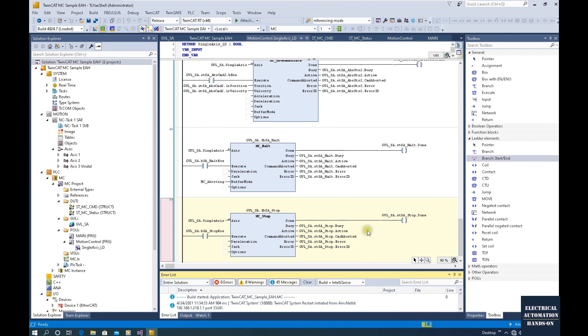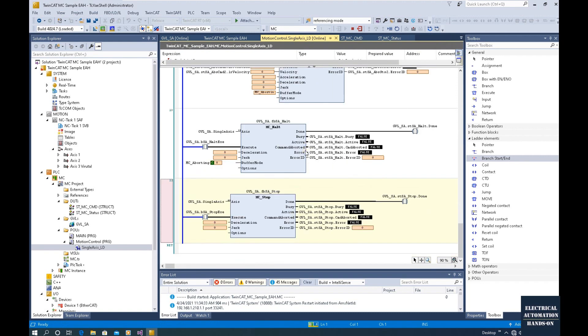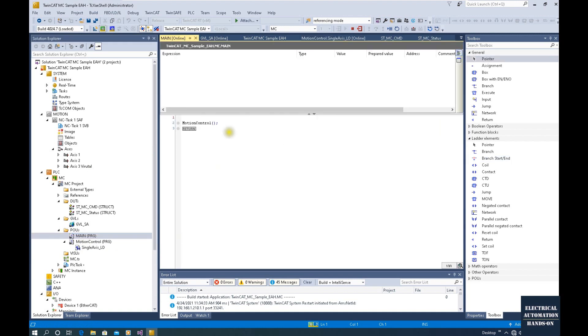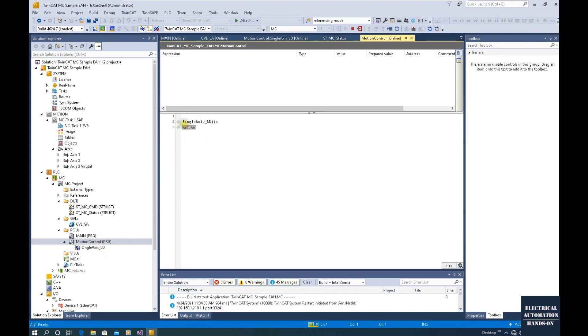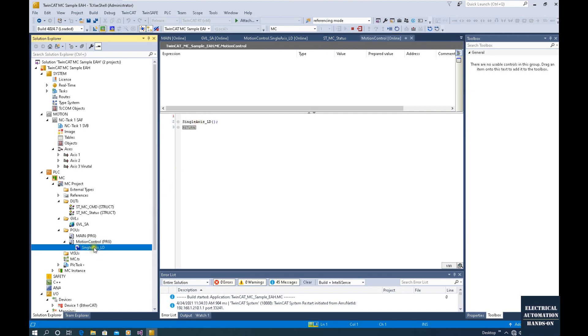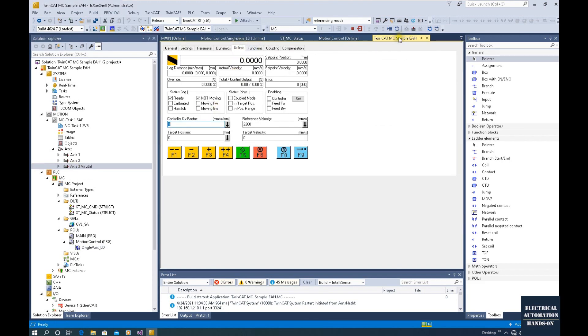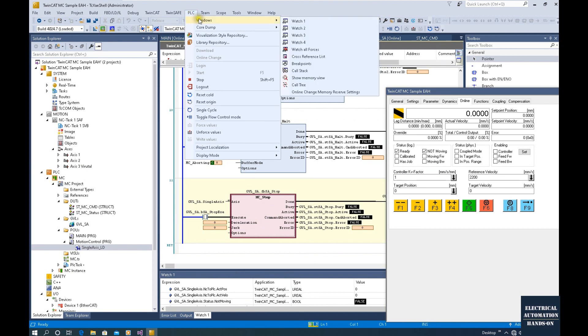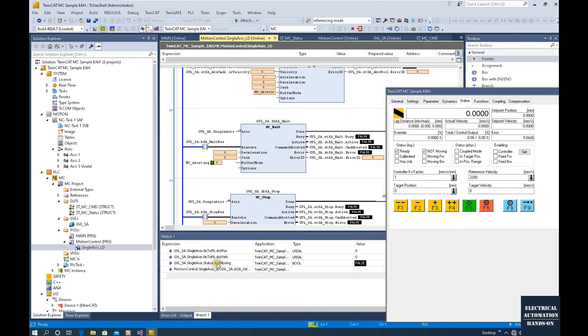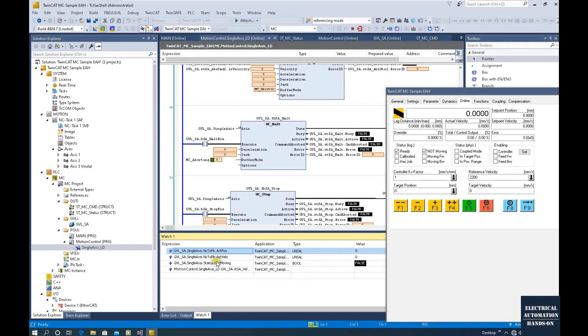Once we see the status change to green link, let's click Login — Login means we are downloading this program. Inside this motion control program, it calls the Single_Axis_LD method, and inside that it calls those function blocks. Meanwhile, we can also go to the axis and open the commissioning panel so we can watch the status. Also, you can use the Watch Table: go to the PLC window, click Watch 1 or Watch 2 to turn on the Watch Table. From there you can drag to find NcToPlc actual position and actual velocity to monitor this axis.